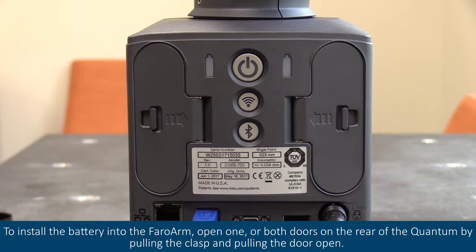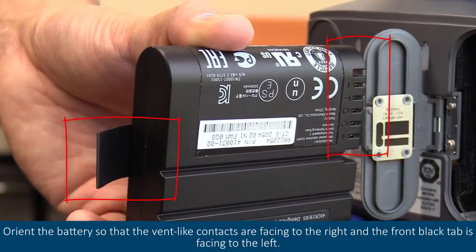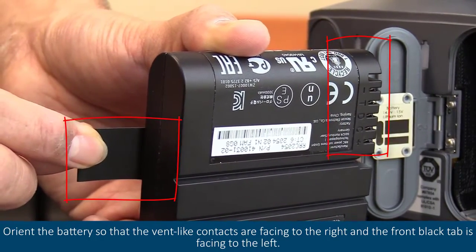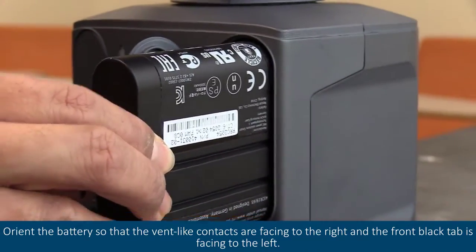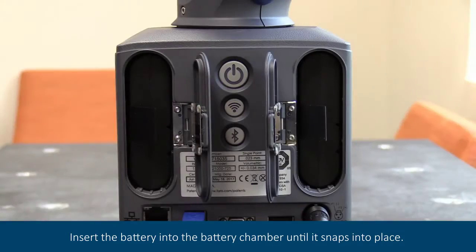To install the battery into the FaroArm, open one or both doors on the rear of the quantum by pulling the clasp and pulling the door open. Orient the battery so that the vent-like contacts are facing to the right and the front black tab is facing to the left. Insert the battery into the battery chamber until it snaps into place.